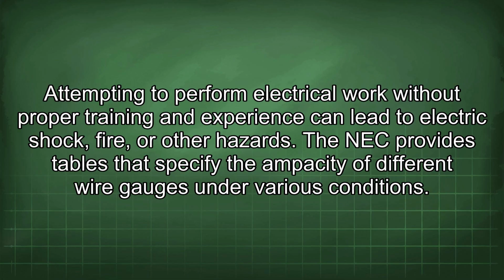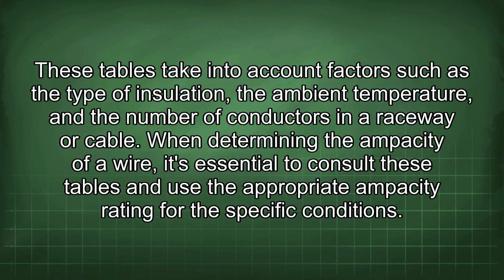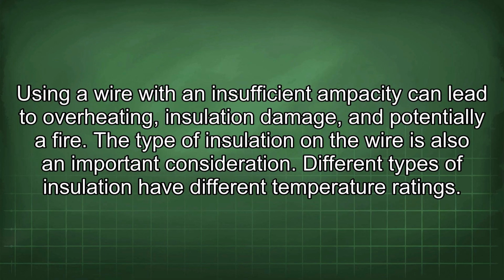The NEC provides tables that specify the ampacity of different wire gauges under various conditions. These tables take into account factors such as the type of insulation, the ambient temperature, and the number of conductors in a raceway or cable. When determining the ampacity of a wire, it's essential to consult these tables and use the appropriate ampacity rating for the specific conditions. Using a wire with an insufficient ampacity can lead to overheating, insulation damage, and potentially a fire.